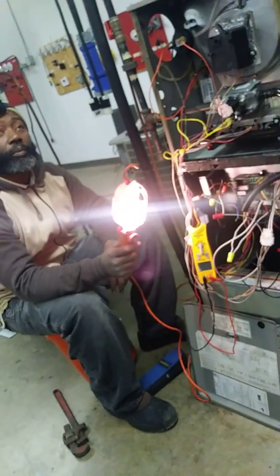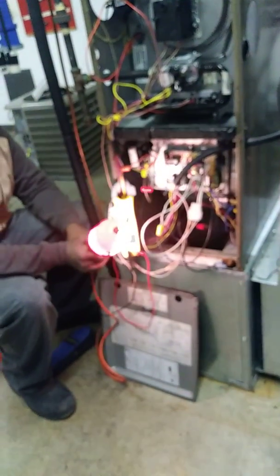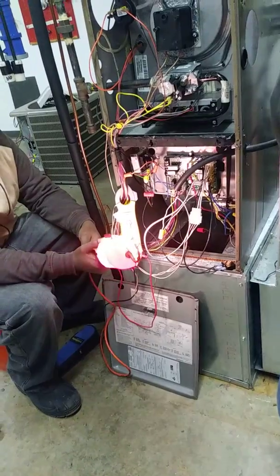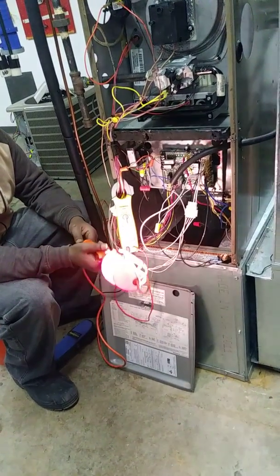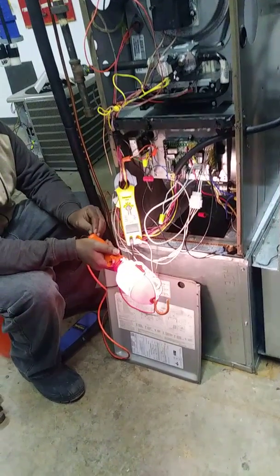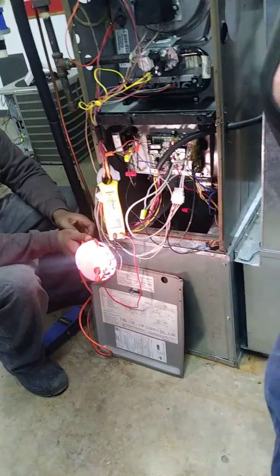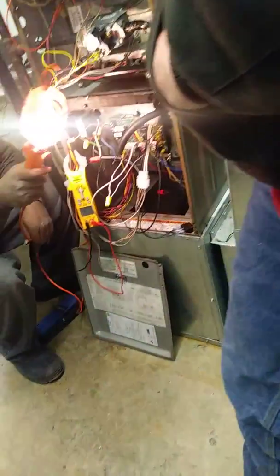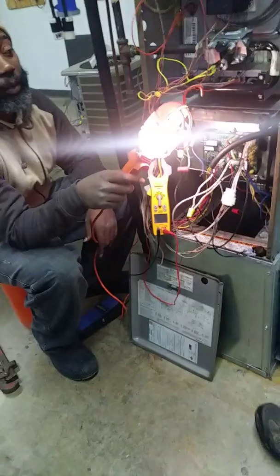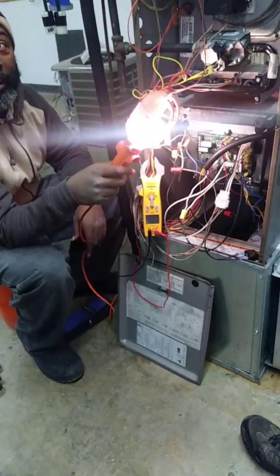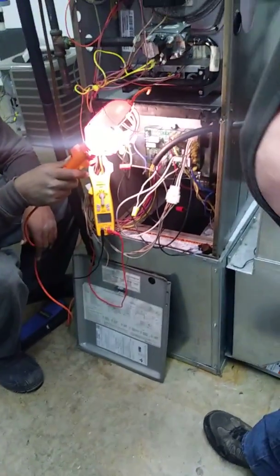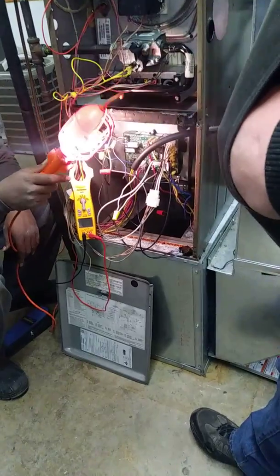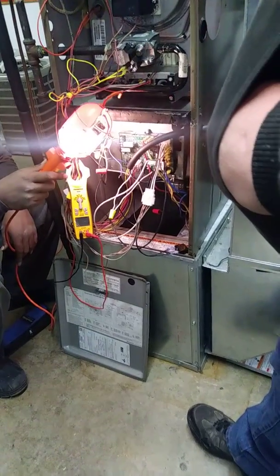Doesn't the flame come on after the gas valve though? Yeah. Is it the flame sensor then? How long is it on? I don't know. I haven't seen the furnace yet. Who told you that? A friend. You said that the furnace turns on for a little bit, but then it turns off. You have to ask him what he means by a little bit. Exactly. Because if it comes on and shuts down within 6 to 7 seconds, then the flame sensor is bad or needs to be cleaned.